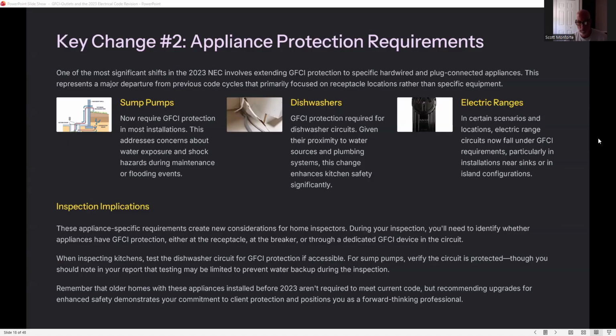One of the most significant shifts in the 2023 NEC involves extending GFCI protection to specific hand-wired and plug-in connected appliances. This represents a major departure from previous code cycles that primarily focused on receptacle locations rather than specific equipment. So sump pumps now require GFCI protection in most installations. This addresses concerns about water exposure and shock hazards during maintenance or flooding events.